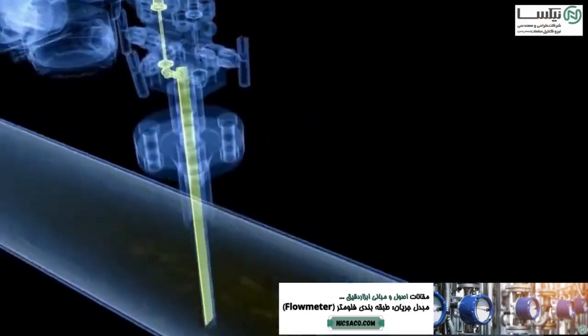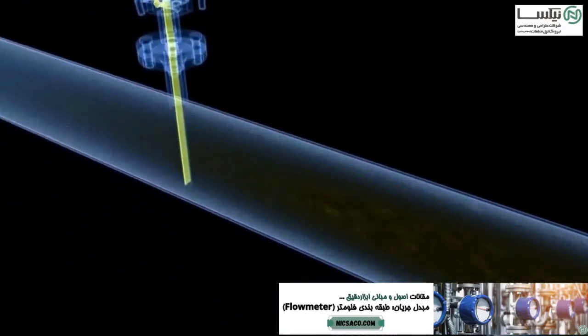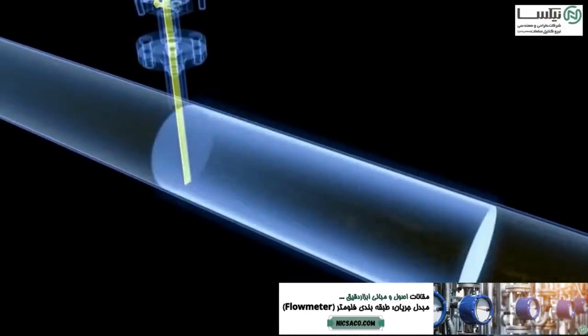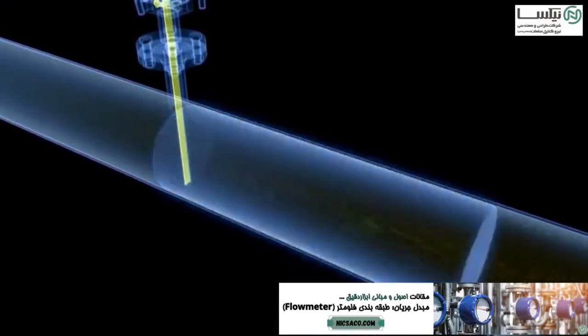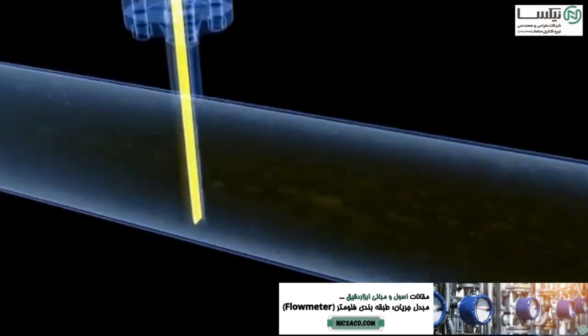As a result, different values are detected in the pressure chambers of the sensor. Higher pressure against the flow and constant pressure on the rear of the Pitot tube. This pressure difference is a direct measure for the flow velocity and thus the mass and volume flow in the pipe. The higher the flow velocity and therefore the dynamic pressure, the greater the differential pressure measured.